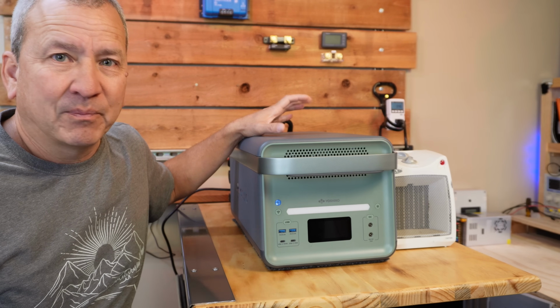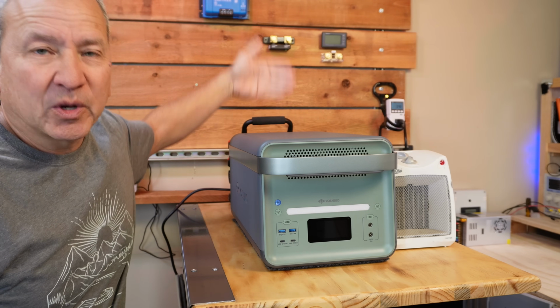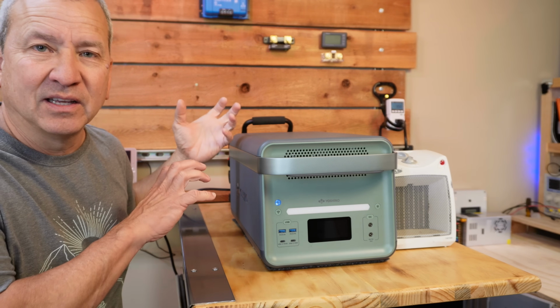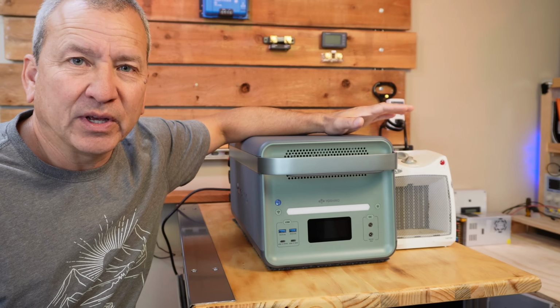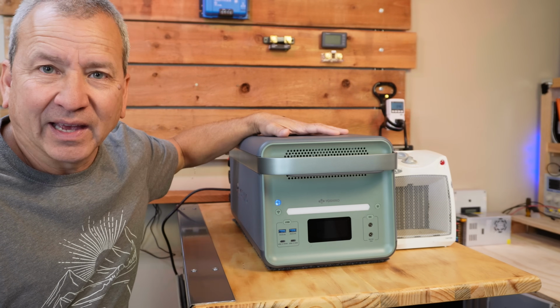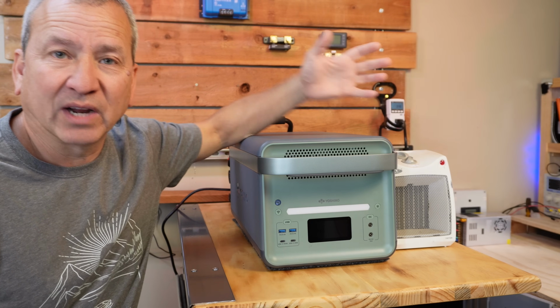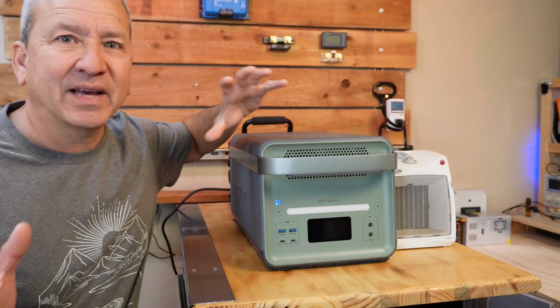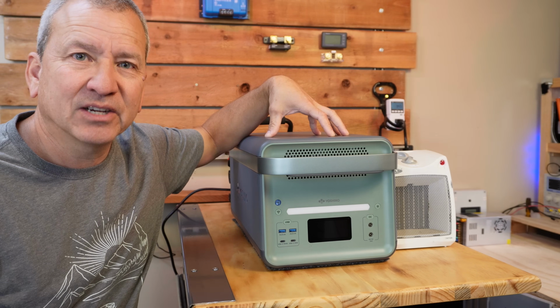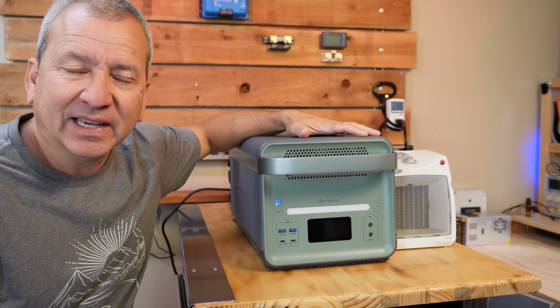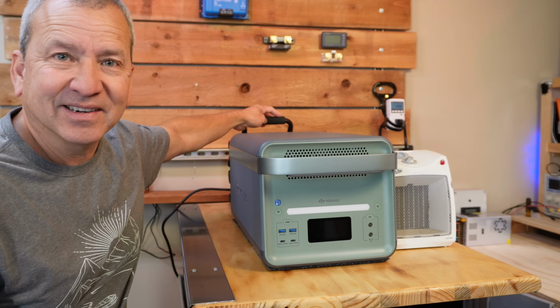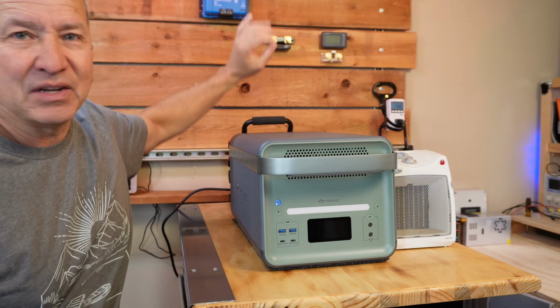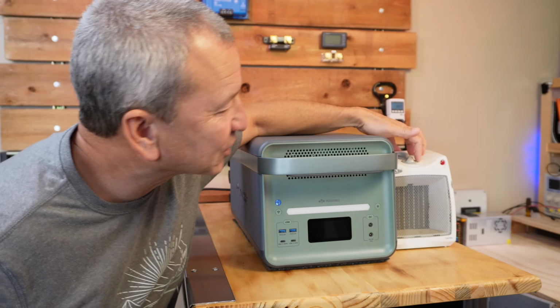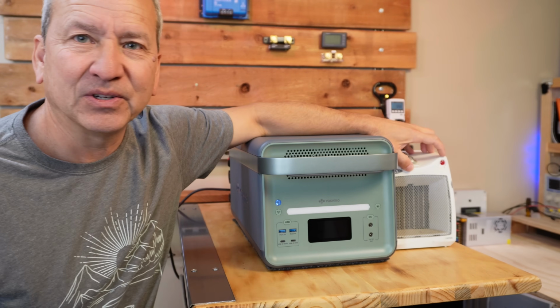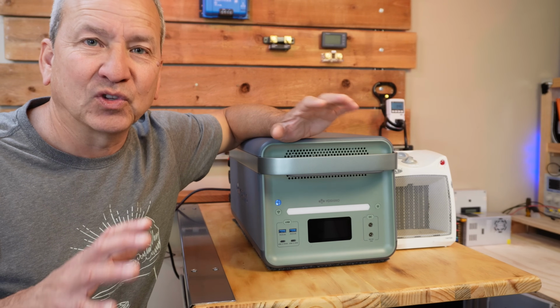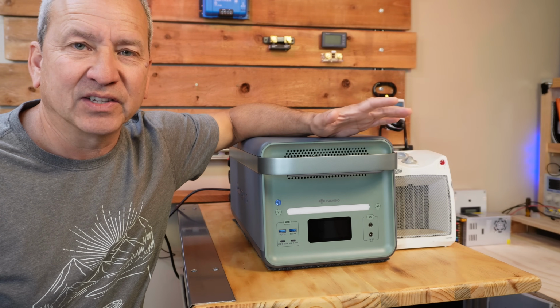Now, when the power goes out and that grid power drops off, it should automatically switch to inverter and battery power and continue to power whatever's connected to it. That automatic power transfer should happen really quick, like 20 milliseconds. So I have a light here that should let us know if there's any flickering, to see how that switch occurs. We'll also have this heater turned on, which has a little light on it too, so we'll see if there's any momentary drop in power during the switchover.